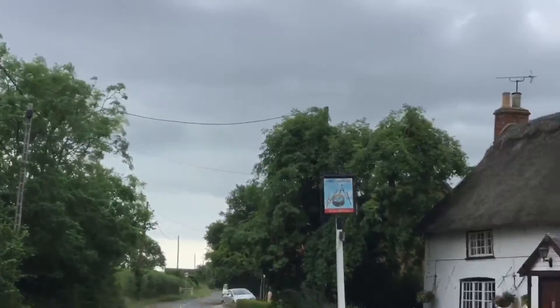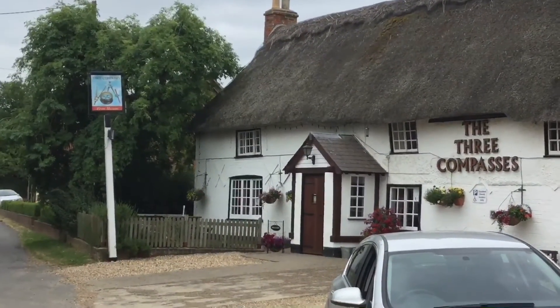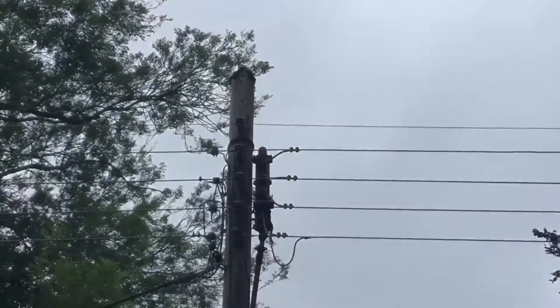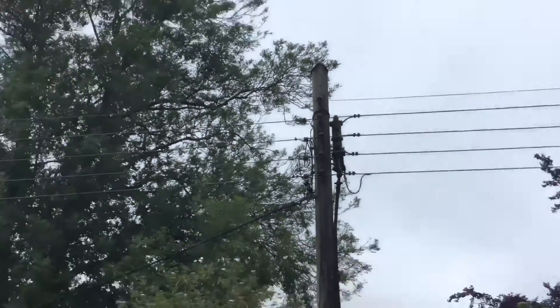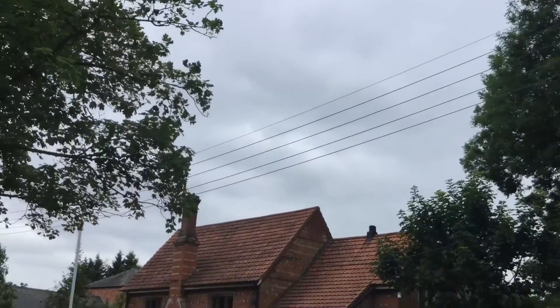The insulated cables now overhead are making their way towards a single phase installation — in this case, the local pub — so line and neutral are taken into that installation. You can often also spot bare overhead line conductors that are the 400 volt three phase and neutral supply, which allows you to tap off a single phase supply from any one line and neutral for each individual dwelling.